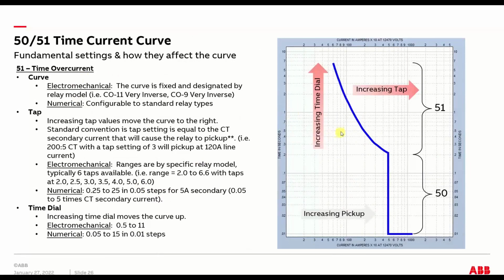Here's some explanations on the settings of the relay. It's back to what I was talking about: tap, time dial, and then curve. This is for time overcurrent. So if you're a time overcurrent, you have your time dial, which essentially moves the curve up and down in time on the time axis, and then your tap, which essentially moves the pickup left and right on your ampere axis.